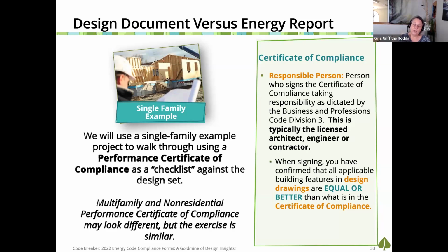You are putting your liability on the line when you're signing, saying, hey, everything in this compliance form, the certificate of compliance, is equal or less than what my design is. My design is going to be equal or better than what's supported in the certificate of compliance, which is setting the bare minimum. And that's what you're signing. So if you don't look through these forms and confirm it supports your design, you're taking a risk by signing it.